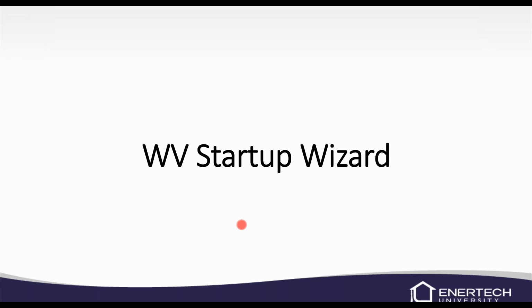So the startup wizard, when you first power up the unit, it's going to send you through the startup wizard. There's a button on the HMI where you can always go back and redo the startup wizard. Let's say you don't have the domestic hot water hooked up right now. You could turn that section off, go ahead and run the unit for your heating needs or cooling, whatever you've got. And then you can go back into the startup wizard once you're ready to complete the domestic hot water.